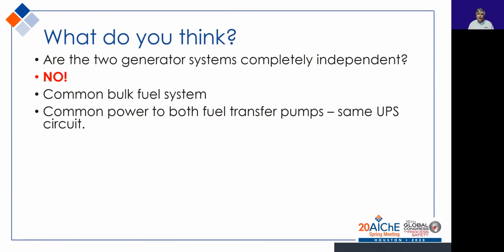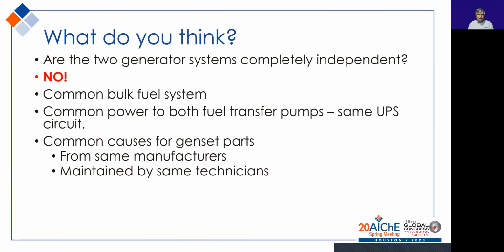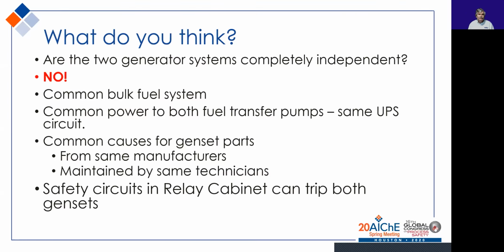to both fuel transfer pumps using the same UPS circuit. By the way, UPS stands for Uninterruptible Power System. But there are a number of faults that can prevent any UPS from providing power. We also have common causes from the genset parts from the same manufacturers, maintained by the same technicians, and operated in the same environment. We have safety circuits in the relay cabinet that can trip both gensets.